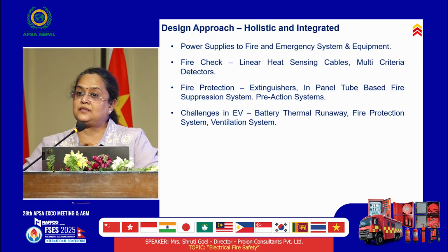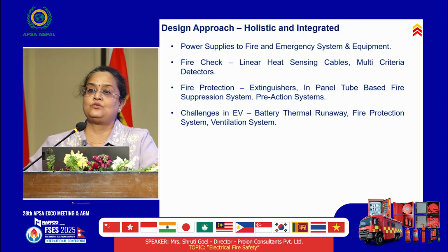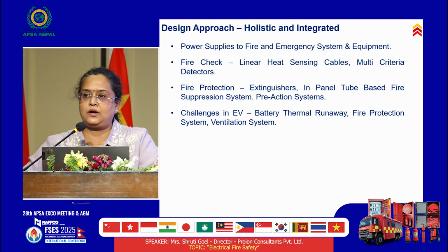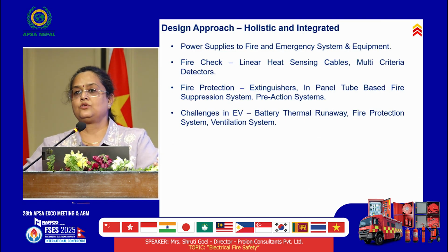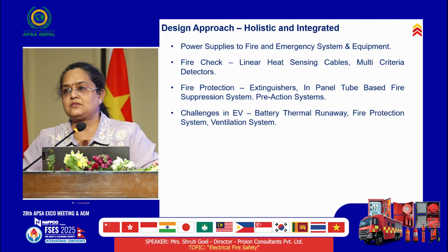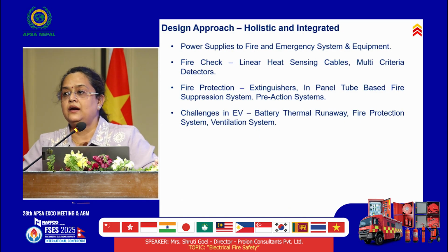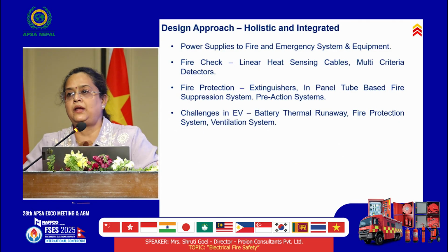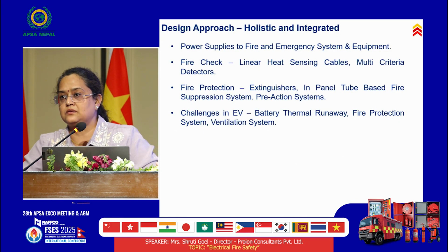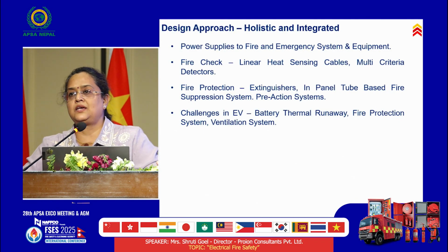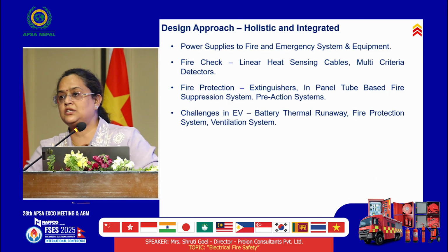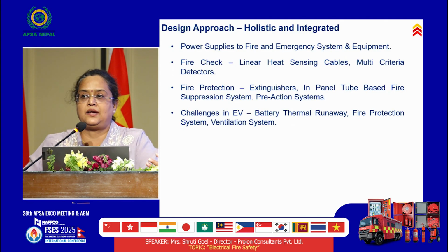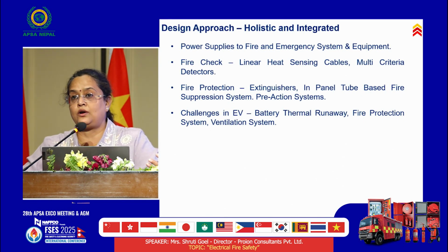What did you notice? That very few lights were switching on. During the design of the system, at least 10% of these lights should remain on UPS, so that there is safety in the hall. Even though it is largely occupied, people should not feel scared or start moving around if the electricity is not there. Emergency switches, the lights should always be on.